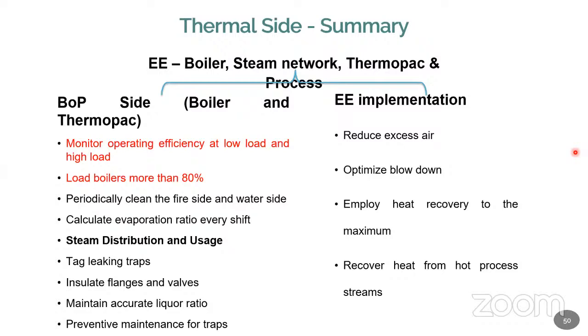Periodically clean the fire and water tubes regularly to avoid soot formation and scale formation. Regularly check the evaporation ratio. ER is a very simple indication. Find out whether this value is the same as the design value or not. And if the value is very low, then you have to take remedial measures to find out why it is lower. Okay.